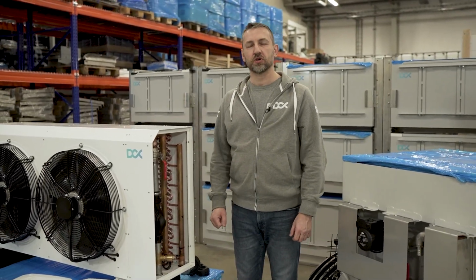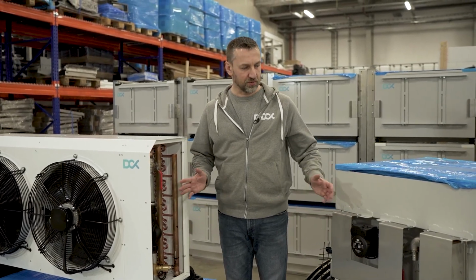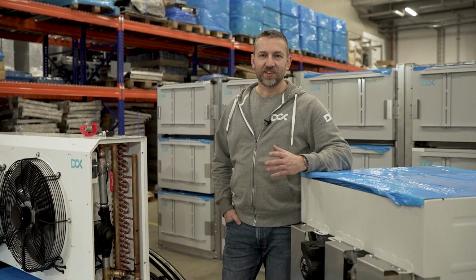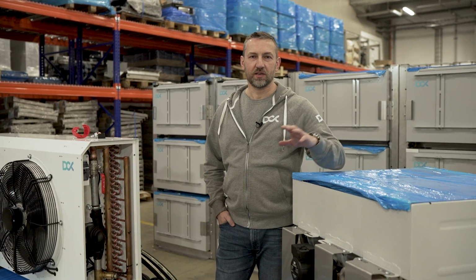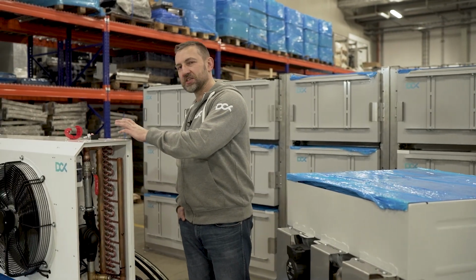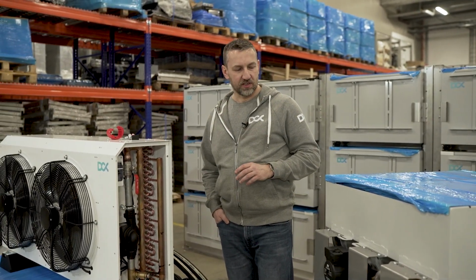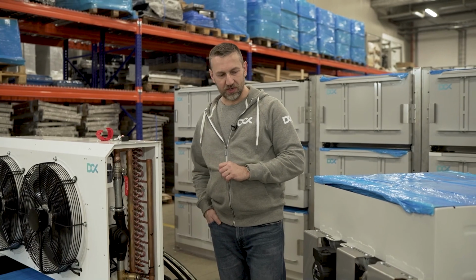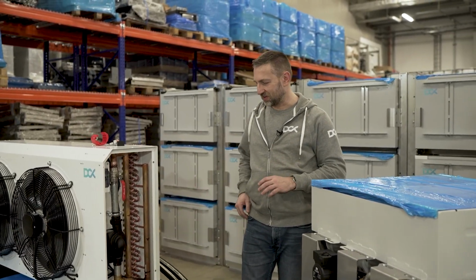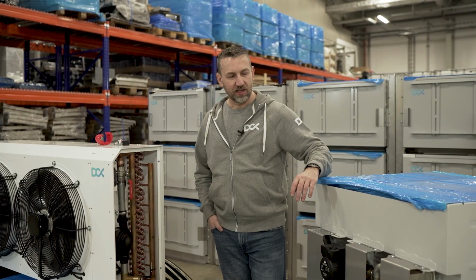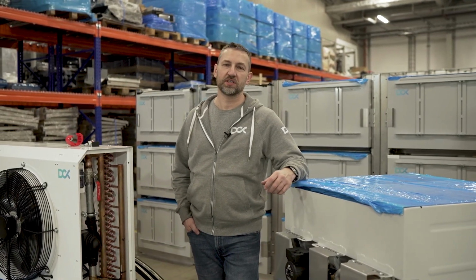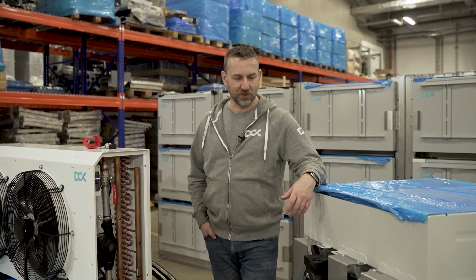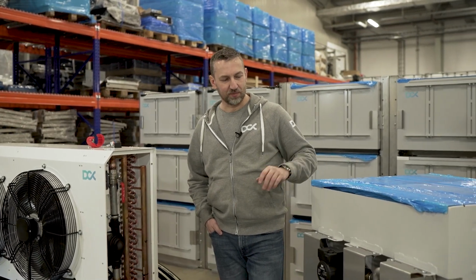And now I can show you how to connect those 2 components together. Next step, we need to connect the immersion enclosure with the ICP40. So, 2 components which must be connected using the provided tubing. As you can see, I gathered lots of small items here which we need. Actually, all the installation, all the commissioning should take less than 1 hour. Well, we did some records locally, but let's do it slowly, step by step.